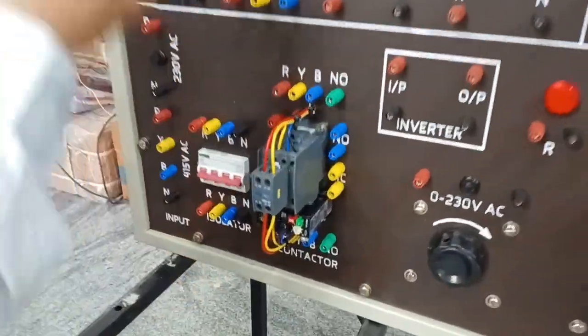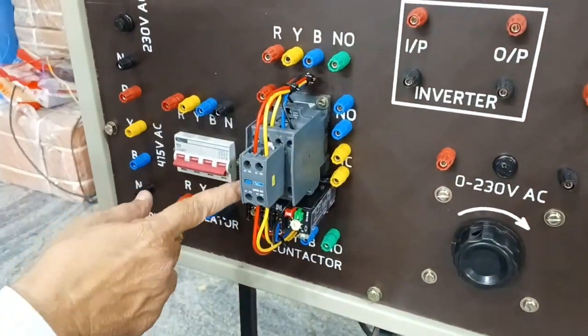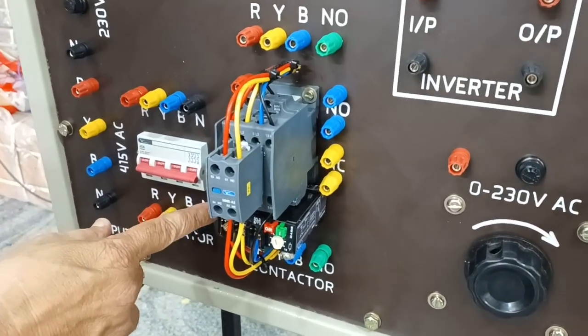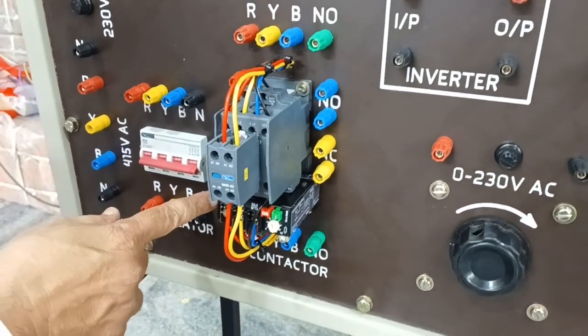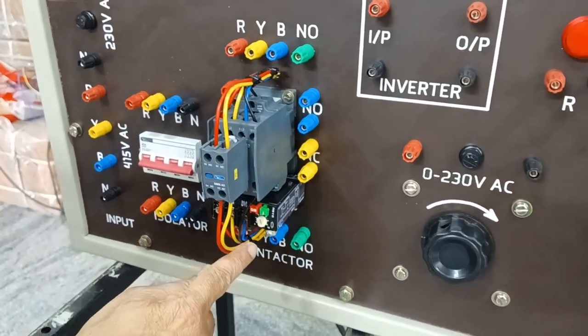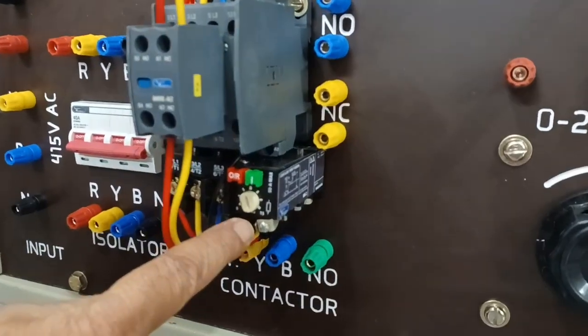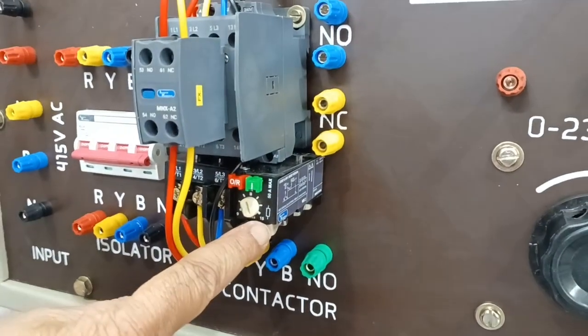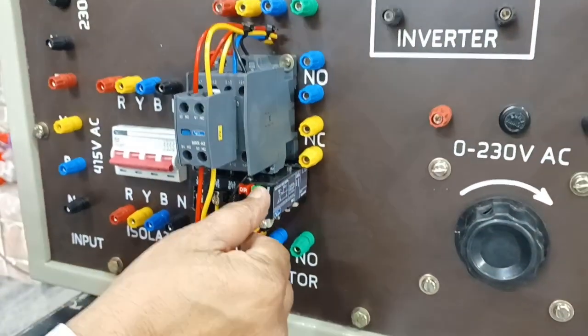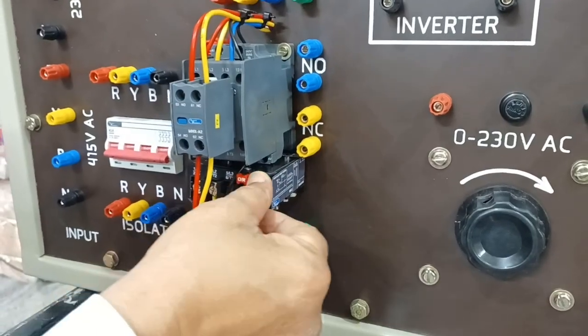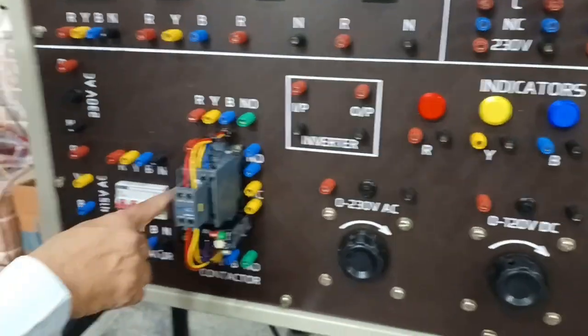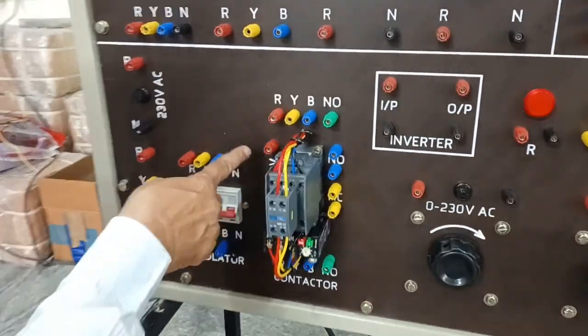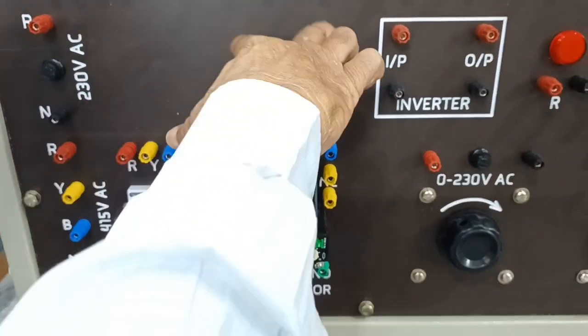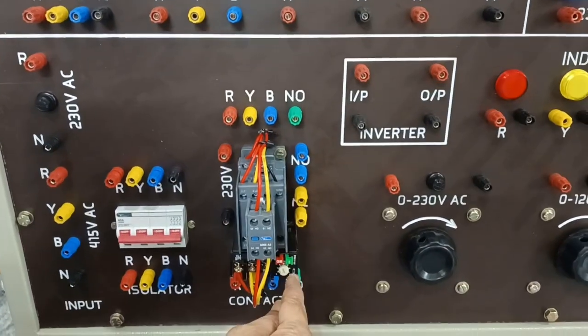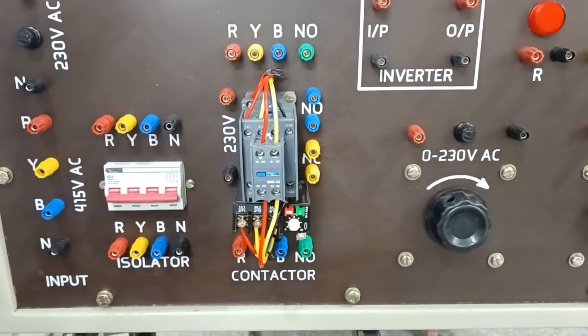The difference between the top and the bottom contactor is here you have OLR. OLR means overload relay. Say this current can be adjusted from 0 to 15 amps. And then if it trips, you need to reset this. Again simultaneously you have auxiliary of 230 volts. This is your input and this is your output. You can adjust your current settings.